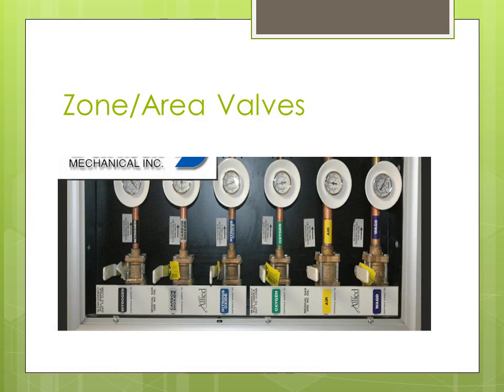So I know I've had problems with some of my older buildings where we did not exercise them, and then when we went to test them, either they were leaking very badly, and we had to have some kind of emergency shutdown to take care of it, or in some cases, we physically could not turn them. They were just frozen in place. So it's definitely something to keep in mind about putting these on schedules and checking them and testing them with some frequency.